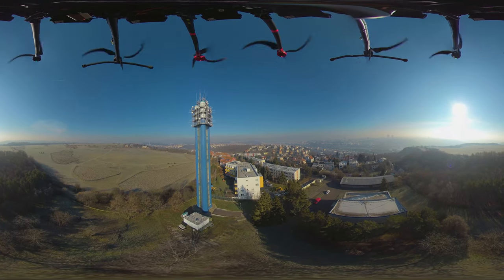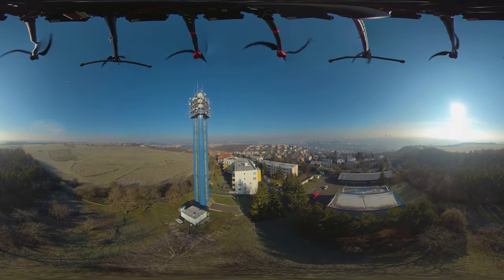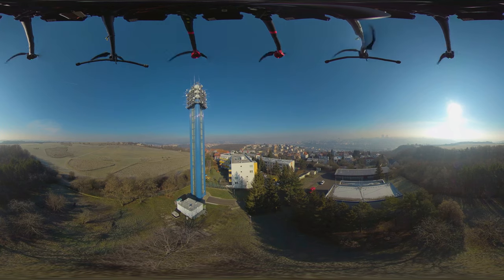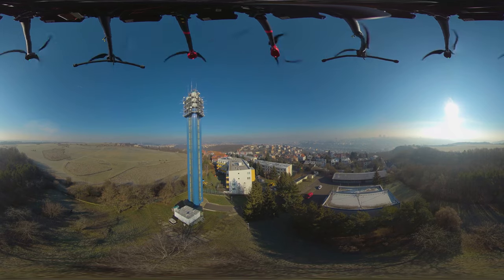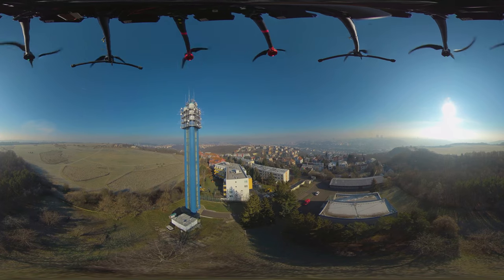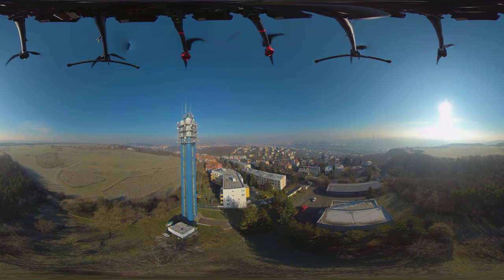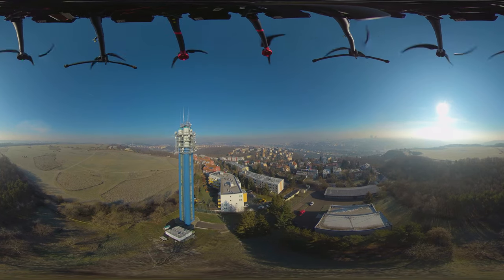How can I explain it? Imagine it like a little tsunami wave that happens in the pipeline. If we just let its power go, it could do incredible damage to the pipes and any connected equipment. That's why our tower is here, on a hill, above Prague. It acts like a kind of enormous expansion tank. It's made of three 50-meter-high connected steel tubes, each with a diameter of 1.8 meters. So, if there's a sudden pressure wave down there in the pipes — all of its power is safely absorbed up in here.